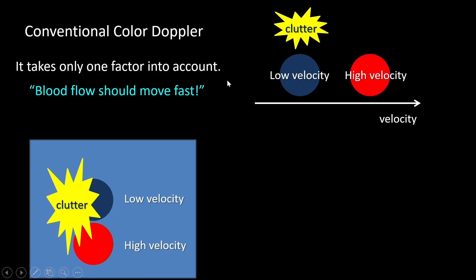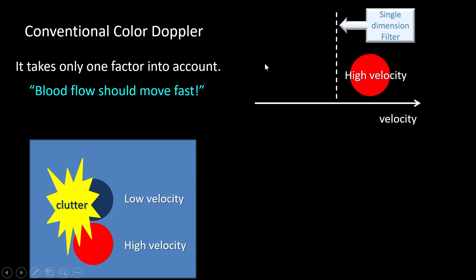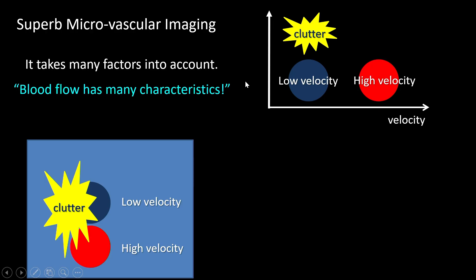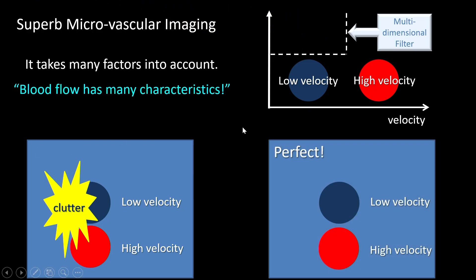The superiority of SMI lies in its filter. Conventional color Doppler uses a high-pass single-dimension filter that only takes velocity into account, eliminating blood flow signals with low velocity — so we can only see high-velocity vessels. SMI employs a multi-dimensional filter taking many factors into account, eliminating only clutter, so we can appreciate blood flow signals with both low and high velocity.